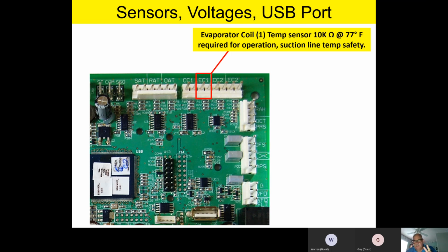Now, if I have a 2-stage piece of equipment where I have 2 evaporators and 2 condenser circuits, then these next 2 sensors make sense. So a CC2 would be condenser coil number 2. If I have a 2-stage unit, it works the same way, and it is required for 2-stage heat pump defrost operation if it's on a heat pump. Right next to it is EC2, which is the evaporator coil temperature sensor, and it's required for 2-stage operation as well. So again, team, remember, if you only have a single-stage unit, you will not have sensors on CC2 and EC2. But if you have a 2-stage piece of equipment, you'll have sensors on both condensers and both evaporators.